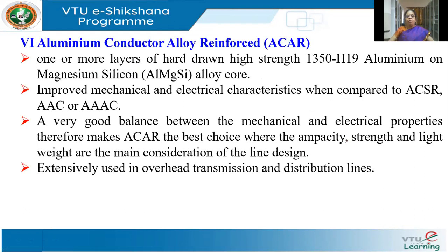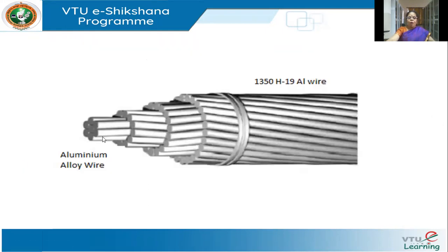Next we have ACAR — Aluminium Conductor Alloy Reinforced. It is similar to ACSR, only the reinforcement is not steel but a magnesium-silicon alloy. This has improved mechanical and electrical characteristics compared to ACSR, AAC, or AAAC. There is a very good balance between electrical and mechanical properties, with very good ampacity (current carrying capacity), good tensile strength, and lightweight. All these make it a very attractive material for overhead transmission lines at higher voltages. The centre is aluminium alloy reinforcement, with aluminium 1350H19 wire on the outside.